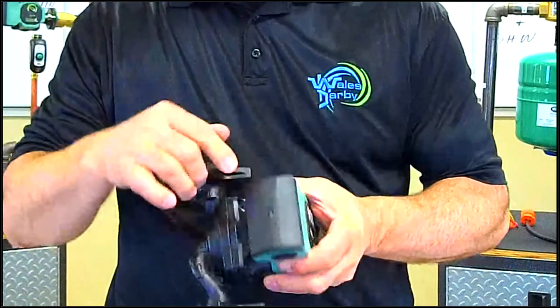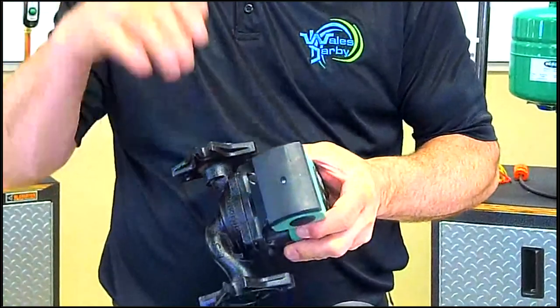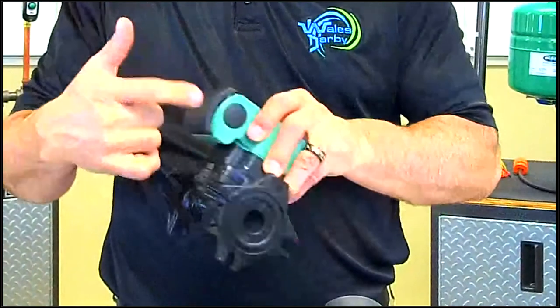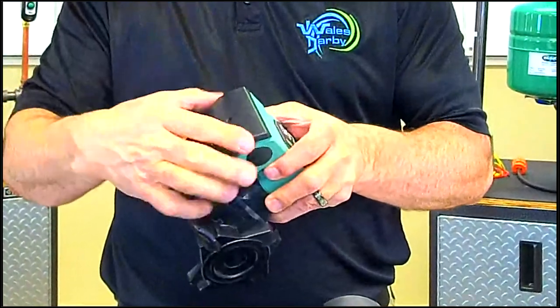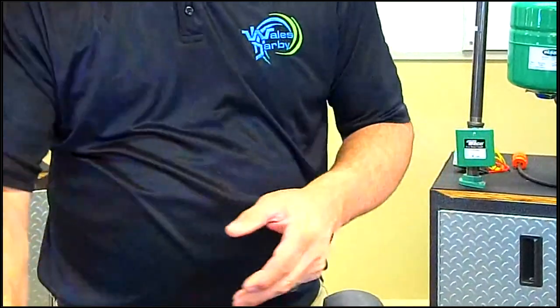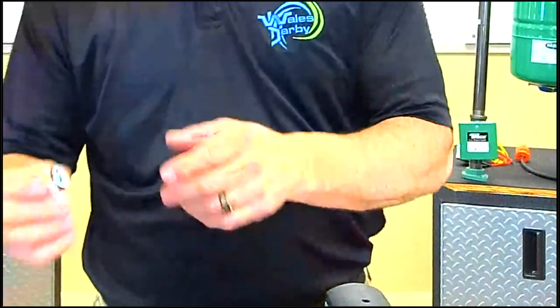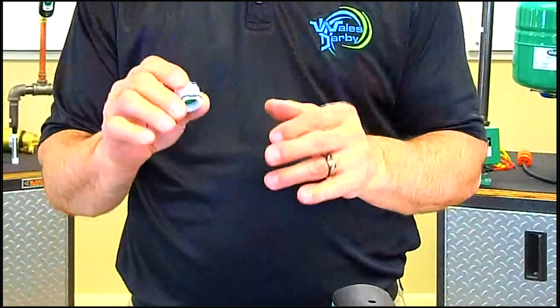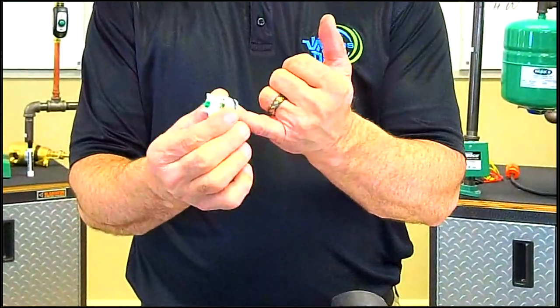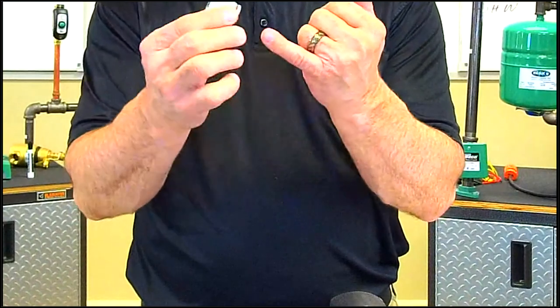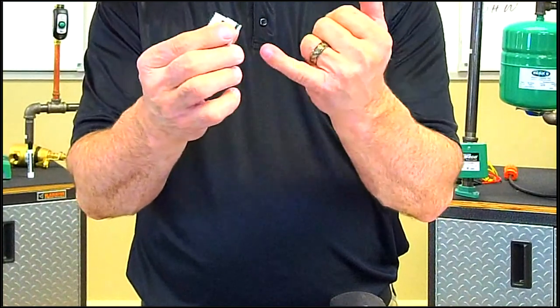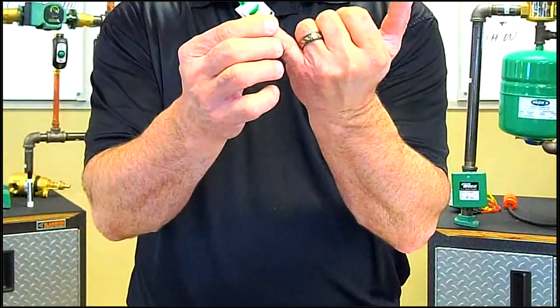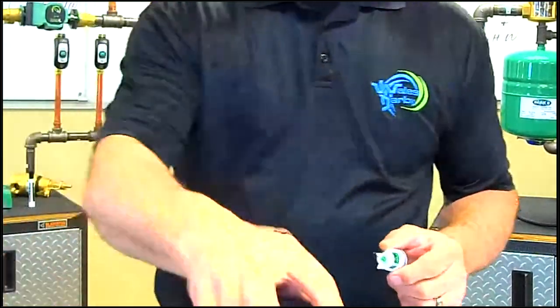Behind this cover, we have a pull away. There's about 6 inches of wire, and you can wire top or bottom with your connector. Very easy to get to. All of the circulators, except the OEM version, come with an integral check valve. So when the water flows through, it pushes the check valve open.